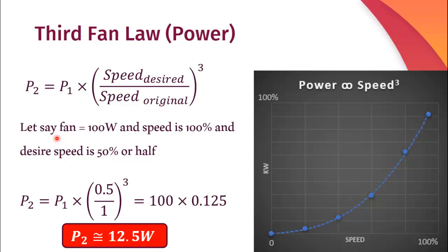Let's say the total power of the fan is 100 Watt at rated speed and now we want to reduce the speed to 50%. So after putting the values, the new power at half speed comes out to be 12.5 Watt, which is almost 8 times less power at the rated speed. So now if the fan consumes 8 times less power, it means that our electricity bill will also be reduced.